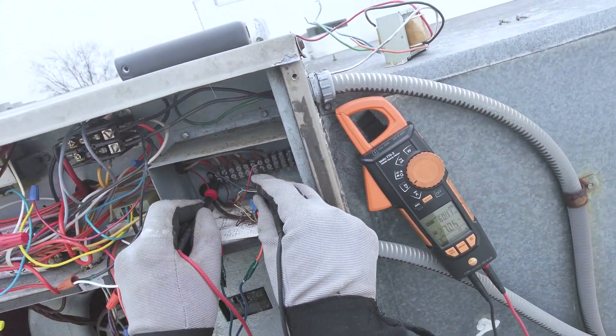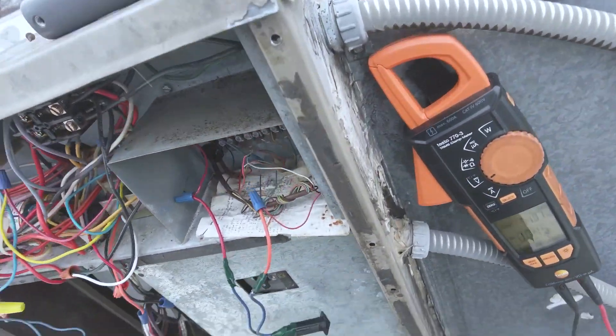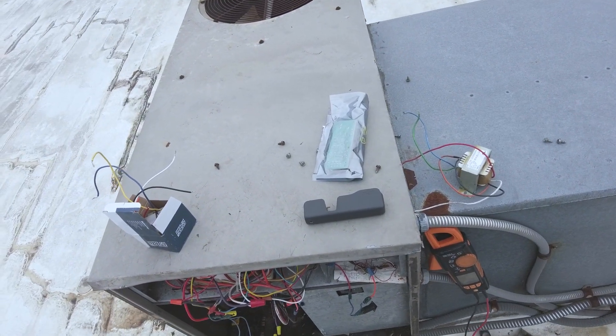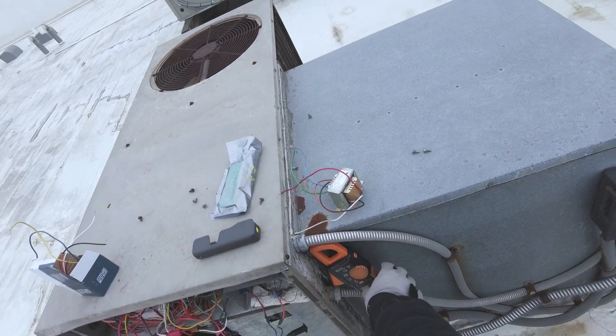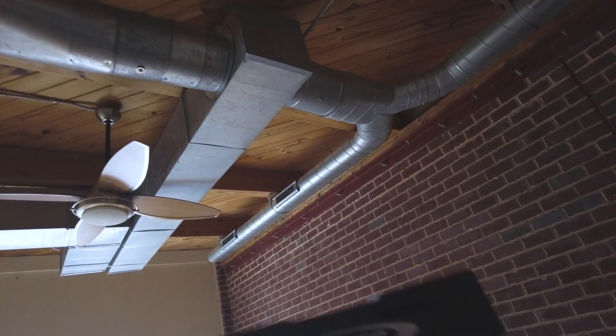Okay, we'll finish wiring that up. Doing good. Now I just go down there and get my zone board buttoned up. It should be good to go. It ran, but the voltage was only getting like 12 volts — basically a short to ground, only getting 12 volts between the cabinet and the hot wire. I wound up finding the short was basically the whole thermostat wire was shorted.